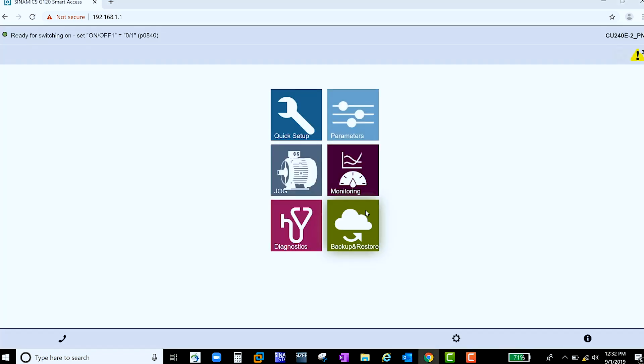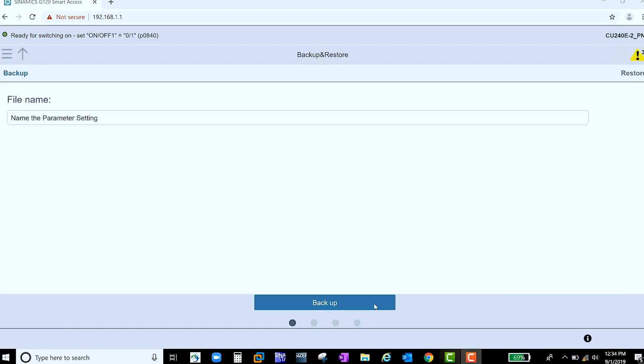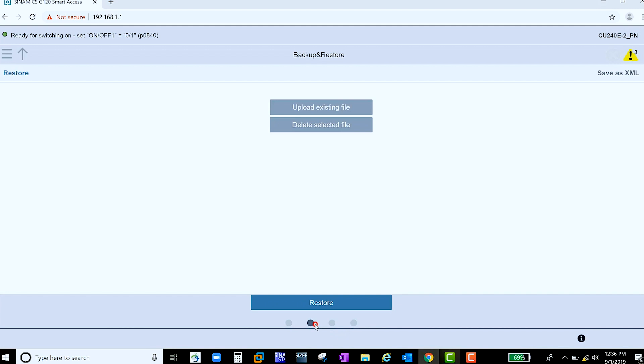Now that the drive has been commissioned successfully, we can go to Backup and Restore to save our settings. Here you can name the parameter setting whatever you would like. If you would like to access these settings and any others saved on the module, go to the second circle here, and you'll see all the options saved, where you can easily upload onto any G120 drive you would like.